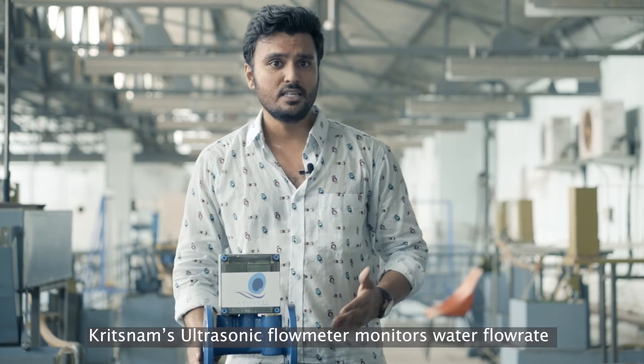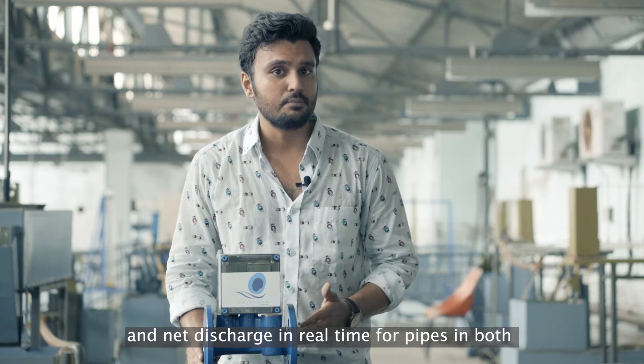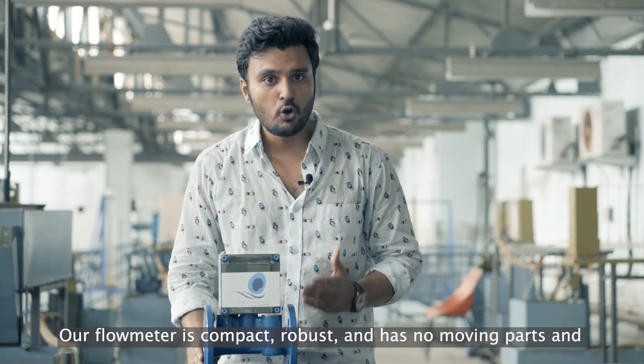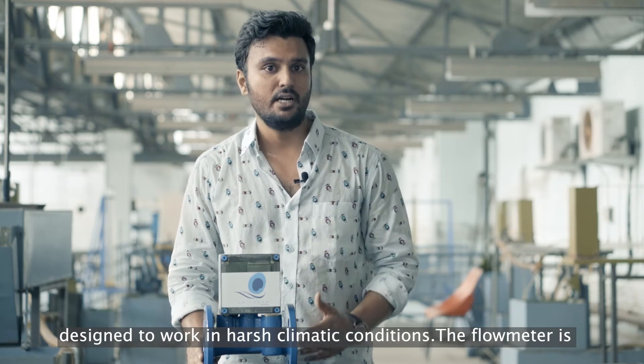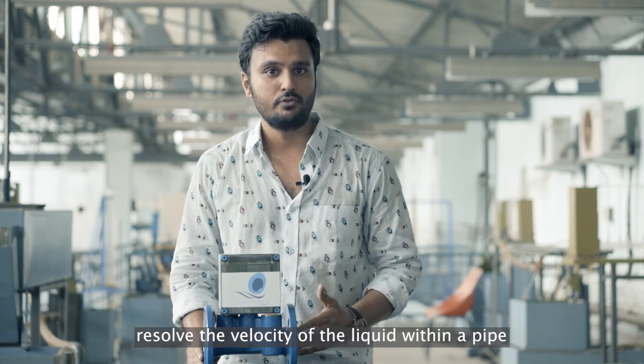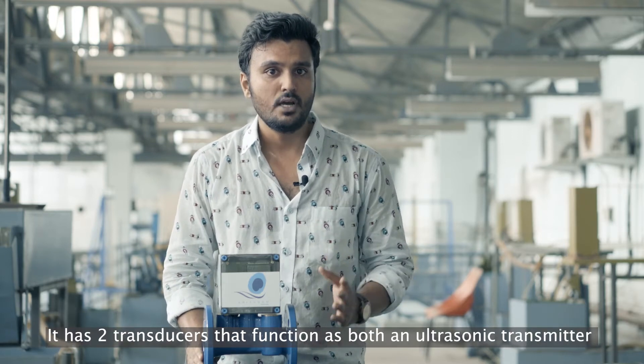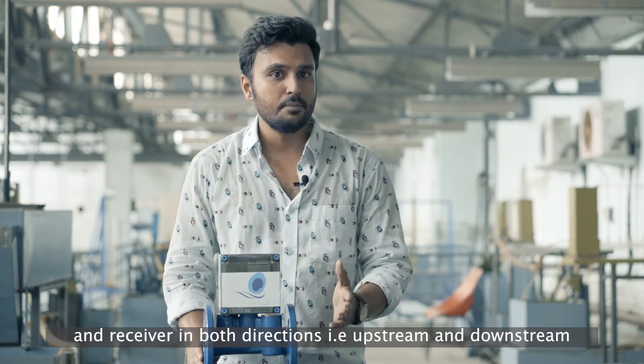Kritsnam's ultrasonic flow meter monitors water flow rate and net discharge in real-time for pipes in both industries and domestic applications. Our flow meter is compact, robust and has no moving parts, and is designed to work in harsh climatic conditions. The flow meter is based on the ultrasonic transit time principle. It uses sound waves to resolve the velocity of the liquid within a pipe. It has two transducers that function as both ultrasonic transmitter and receiver in both directions — that is upstream and downstream.